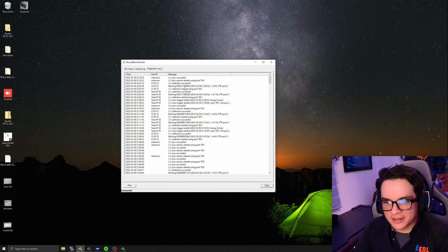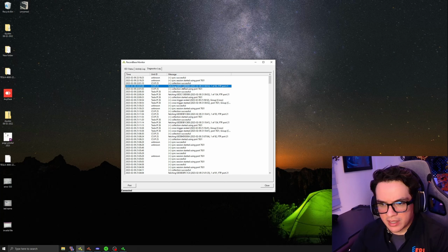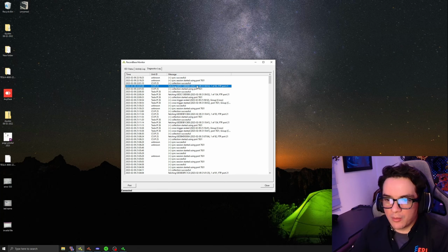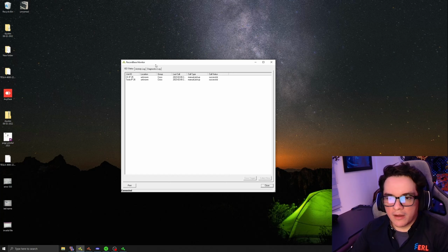Then we have the diagnostics log, which is a little bit more difficult to read, but you're going to be able to see that it's fetching records and also downloading them. For example, here I was downloading a record a little while ago. It says fetching and a series of numbers and letters. Then what time was the trigger of the record, and that it's 1 out of 93 records over FTP port 21. So that way I know that it's collecting the records. So this is going to be a very handy tool, so we know that the system is working properly.